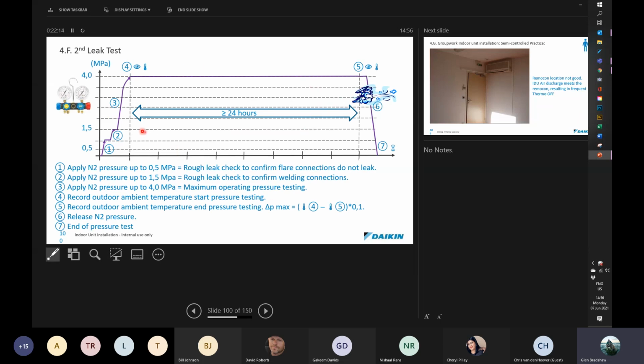This graph pertains to the different pressure testing stages. So basically you take it to 0.5 MPa. It's a rough leak check. Check your flare connections. Walk around with your ears. Make sure that you haven't missed a weld somewhere. Generally what will happen is the pipe will pull out of the socket.